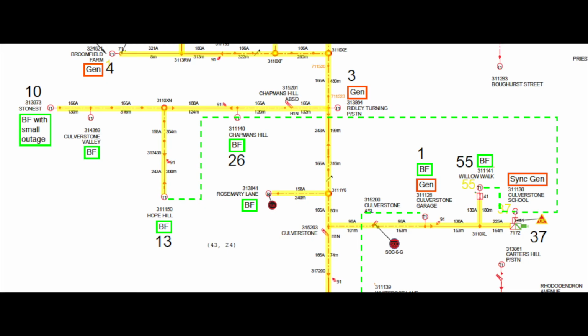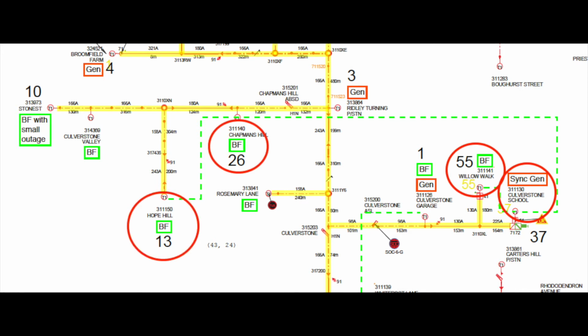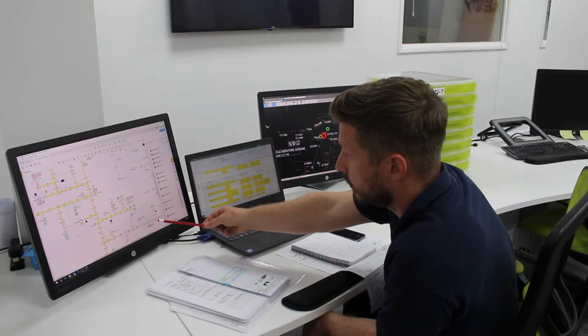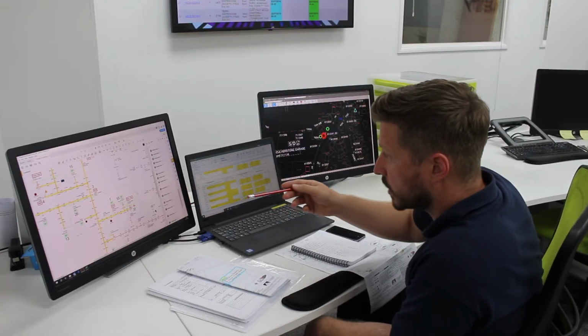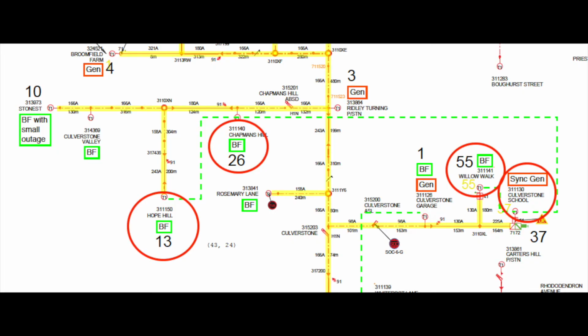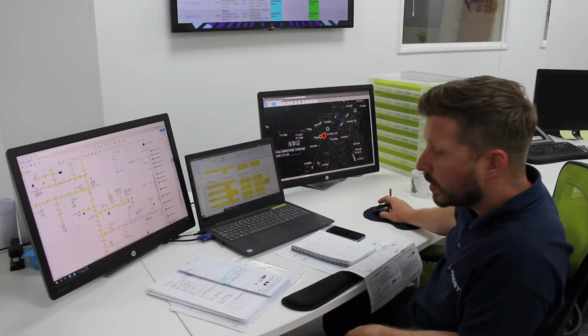If we come across the network this way, this is where it starts to get a little bit more complicated. We've got Culverston School, which you're able to interconnect with Willow Walk and Chapman's Hill and Hope Hill, and as you can see, there's a significant number of customers on all of the transformers: 37, 55, 26 and 13. So what we're going to do, again, is apply backfeeds between the substations, remove the LV fuses, create a point of isolation at each pole transformer, and then again synchronise the generator on at Culverston School, so entirely removing the customer minutes lost on that part. That's a significant number. It is. I mean, that really is a significant number.